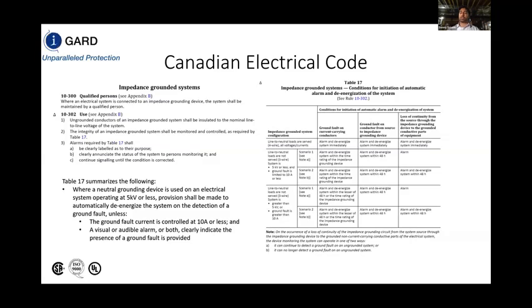Table 17 gives you the instances of when we have to initiate alarm or de-energize the system based on the condition that we're facing. As manufacturers of resistors and relays, we also have to monitor for ground faults in the system, which is denoted by this column here. We have to look for short circuit condition on the NGR, which is denoted by this column in the middle. And we also have to monitor for the open circuit scenario on the NGR, which is a loss of continuity from the XO point to ground.